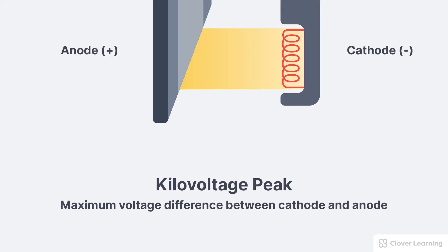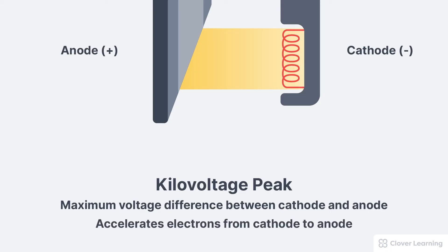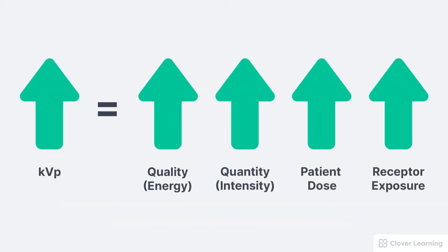So let's review. Kilovoltage peak, or KVP, describes the maximum voltage difference between the cathode and anode during the x-ray exposure. KVP is responsible for accelerating electrons from the cathode to the anode. If we increase the KVP, this will increase the x-ray beam quality — that's the energy — increase the x-ray beam quantity — that's the intensity or number of photons — increase the patient dose, and increase the receptor exposure. These relationships are true when only the KVP is changing, using a fixed technique that's not AEC, and no other variables are changing.